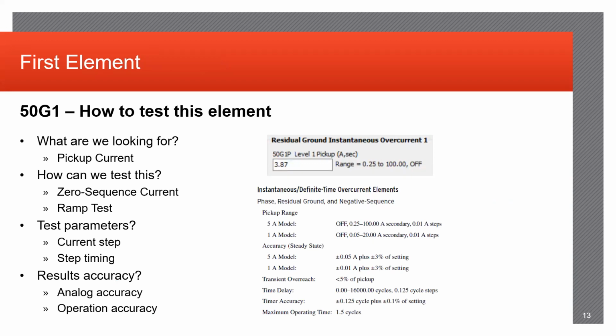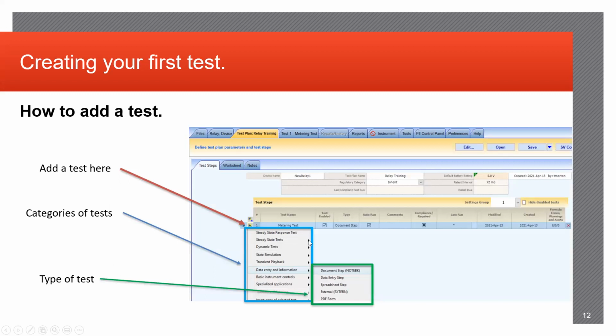So I'm not going to go too deep into this. I'll save that for Paul's relay course, but this is just an overview of some of the different types of tests. For example, this first one here, a 50G1. What we're looking for here is the residual ground overcurrent element that the relay has identified and is going to utilize in its protection. This will be done by identifying the pickup current, testing the zero sequence, and utilizing a ramp test as previously shown in this slide, which would be under one of the steady state tests.